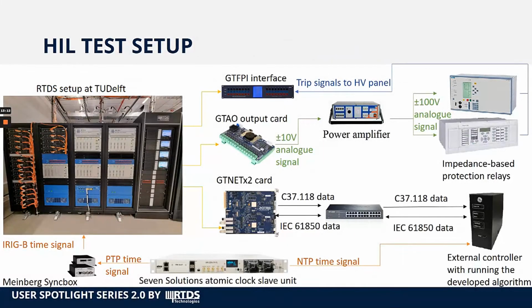Moving on to the hardware-in-the-loop testing setup. On this slide, we have the hardware-in-the-loop test setup we use to test the developed algorithm together with impedance-based protection relays. On the left-hand side, we have the RTDS setup at TU Delft, and we used GTAO output cards together with a power amplifier to provide input values to the impedance-based protection relays, which in turn provided feedback to the RTDS simulator using the high voltage panel on the simulator.